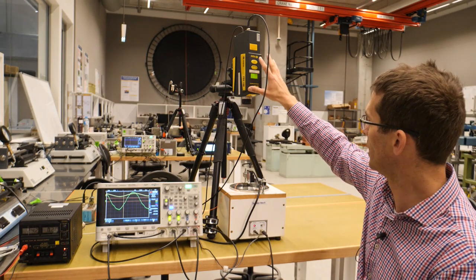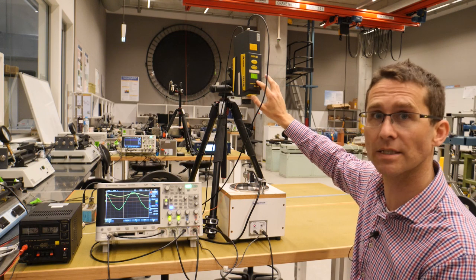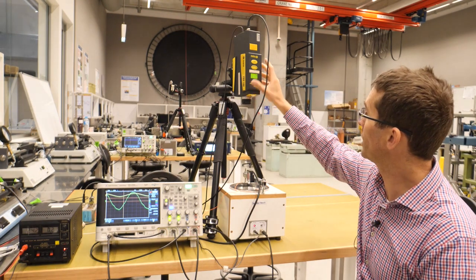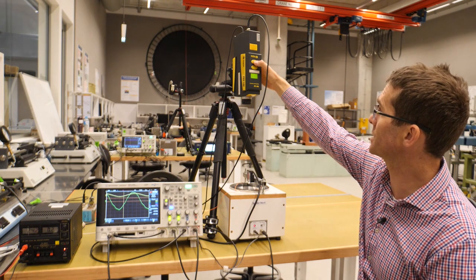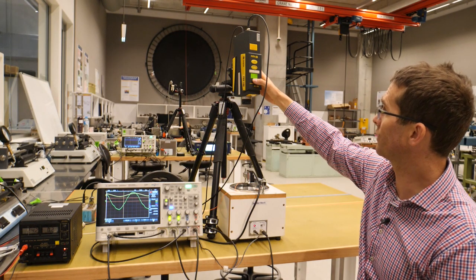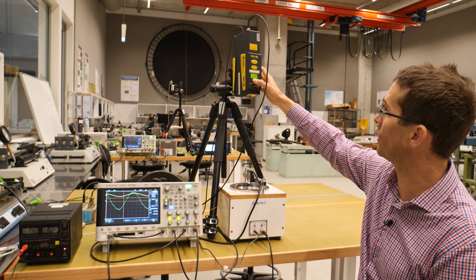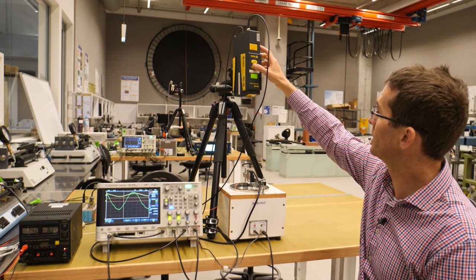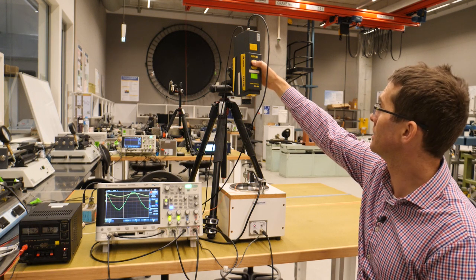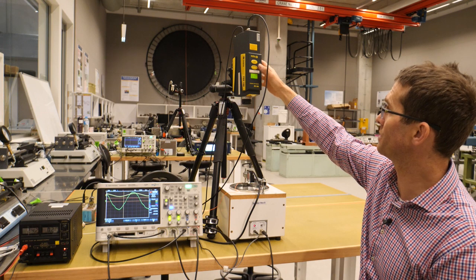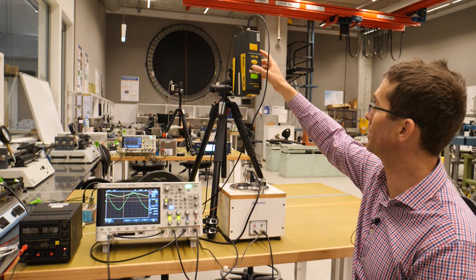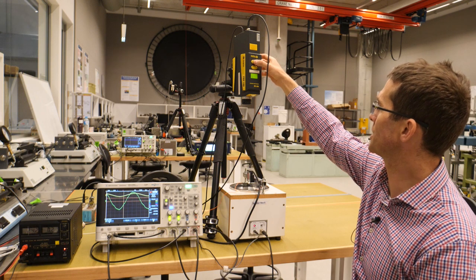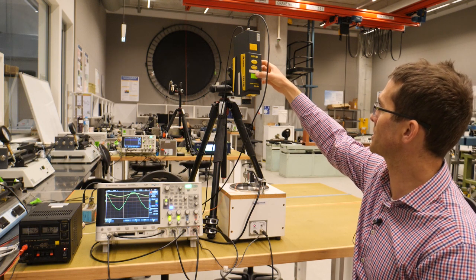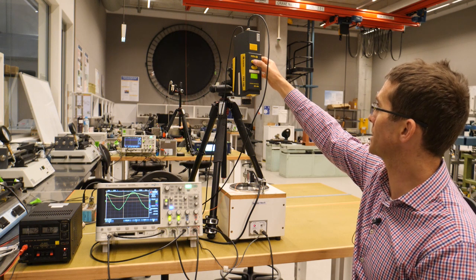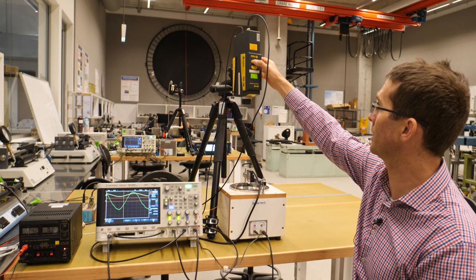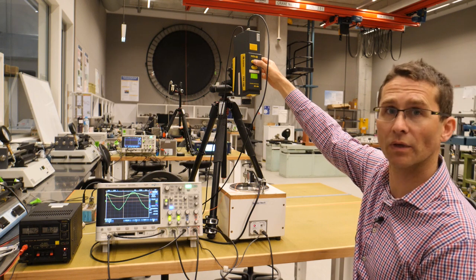A second transducer in use is this laser Doppler vibrometer, which measures velocity. Here we have the opportunity to adjust a number of settings, including the velocity sensitivity, from 500 millimeters per second per 4 volts to 100 to 20, 20 being the most sensitive and 500 millimeters per second for a 4 volt output being the least sensitive. We can also introduce a low pass filter, which we can set to either off, i.e. 22 kilohertz, to 5 kilohertz, or to 1 kilohertz.